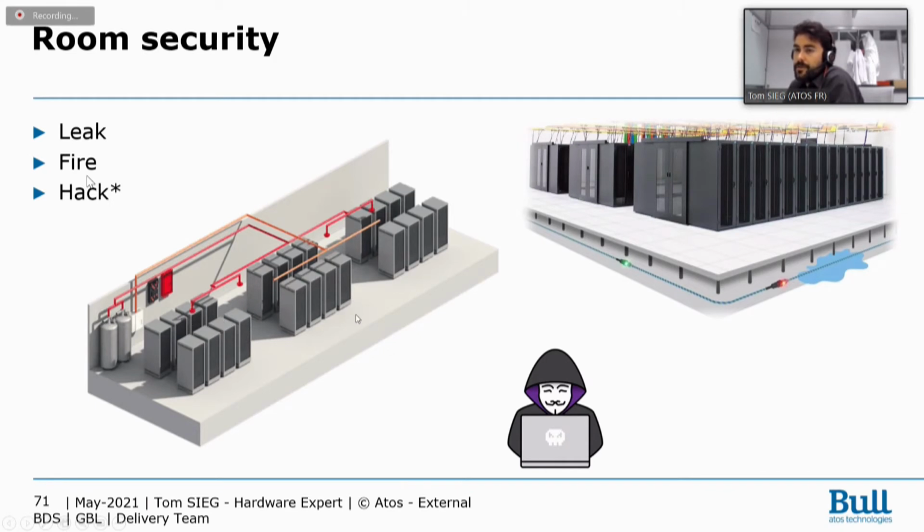Sprinkler water in the data center room is also really efficient, but it can damage your components. So if you put in sprinklers or another fire solution like that, you have to take care about your rack model, just to be sure the rack will prevent water intrusion into the components.